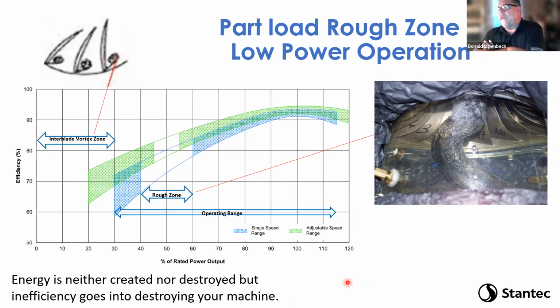And as an old engineer told me, and I found it to be an ultimate truth, right? Any inefficiency that you're running goes into destroying your machine and beating the heck out of your machine. And if they were running down here at 200 megawatts, the efficiencies were down at 60 to 50%, which means if they're running at 200 megawatts and they're running at 50%, that means 100 megawatts is going into destructive inefficiency, right? And so they were running there all night long, continuously.